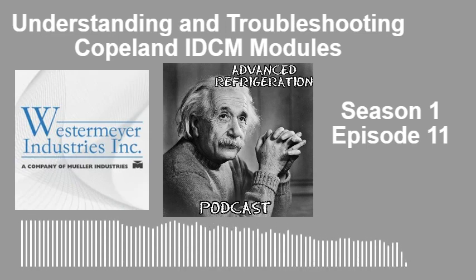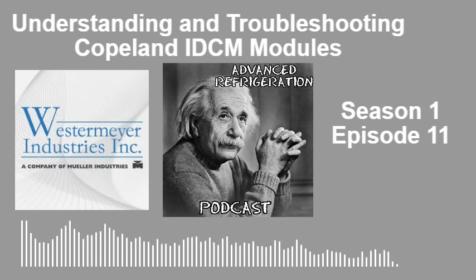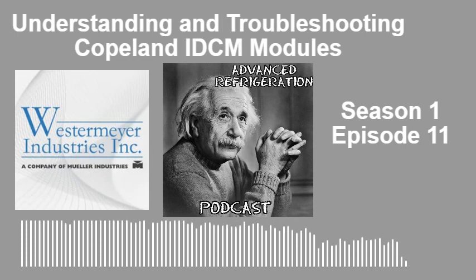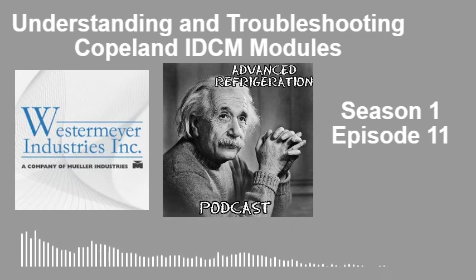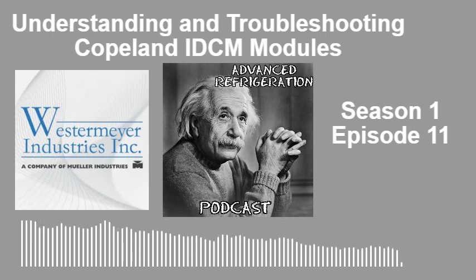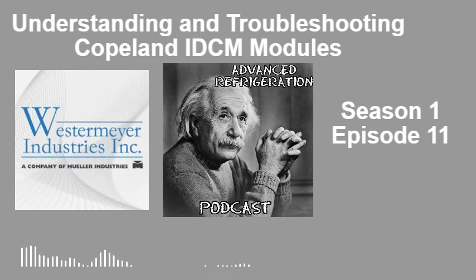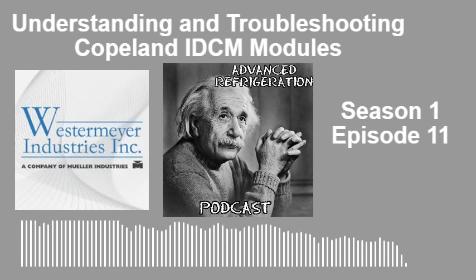Keep that in mind if you see calls happen a lot during the day. Let's say an alarm goes out at noon, you guys are swamped, it's summertime. By the time you actually show up on site, you can't find any known reason why this thing would have tripped out, because now you reset it and it's back up and running. You can't figure out why. You can keep that in mind with rooftop units as well.